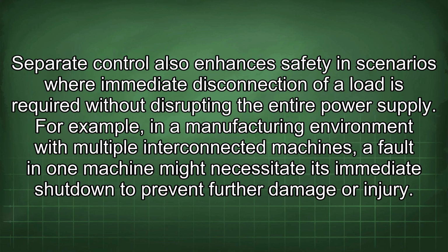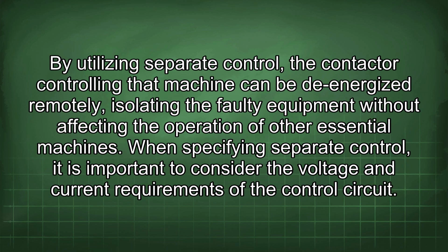Separate control also enhances safety in scenarios where immediate disconnection of a load is required without disrupting the entire power supply. For example, in a manufacturing environment with multiple interconnected machines, a fault in one machine might necessitate its immediate shutdown to prevent further damage or injury. By utilizing separate control, the contactor controlling that machine can be de-energized remotely, isolating the faulty equipment without affecting the operation of other essential machines.